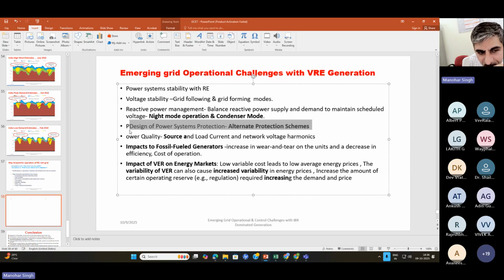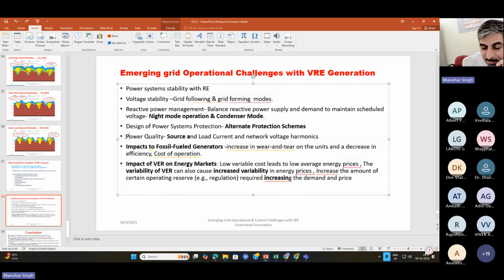So I require some other type of protection schemes which will be able to detect the short circuit and accordingly clear the fault. Those may be signature based, those may be short-lived transient based event, or some other type of strategy. Of course, a lot of research is happening on this side, but still I feel it is quite at the beginning level. Correct? I don't see any industrialized or any commercial type of protection solutions. Of course, a few things are there in academia, but so far as practical applications, things are not there. Still, those lines are protected with the help of line differential schemes.